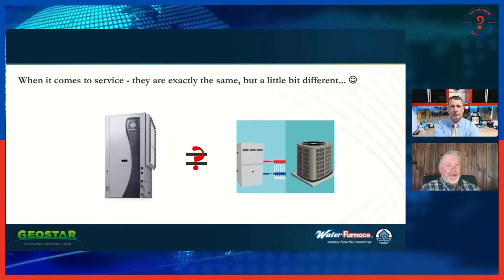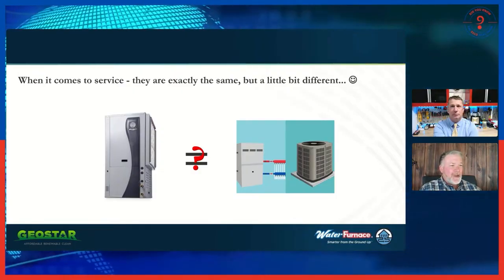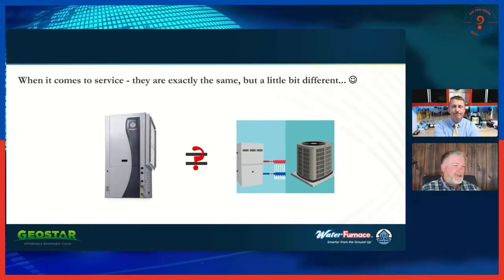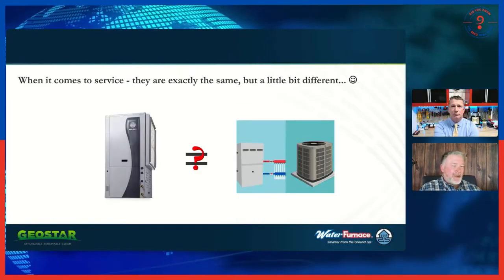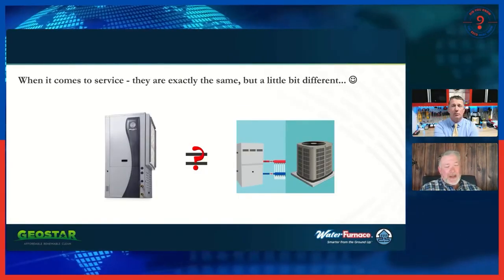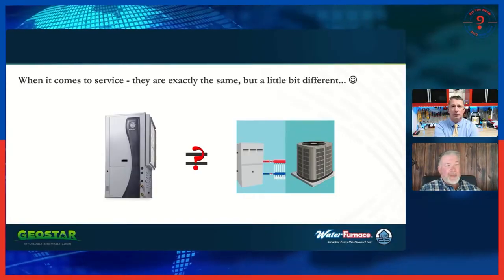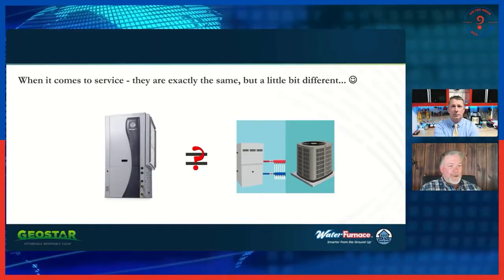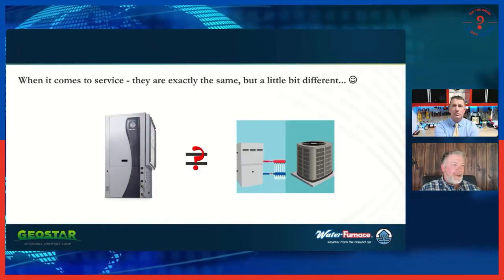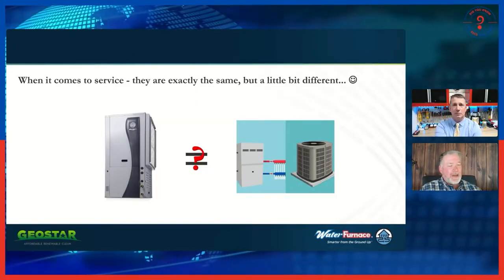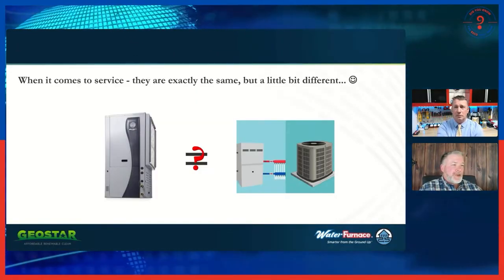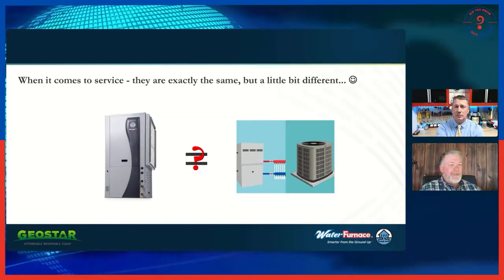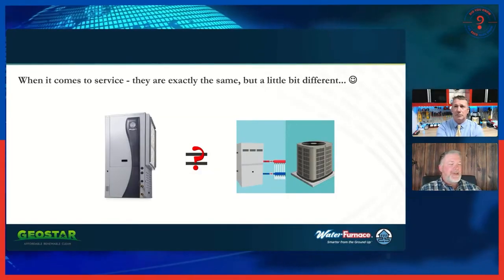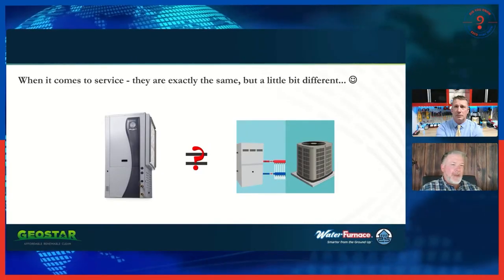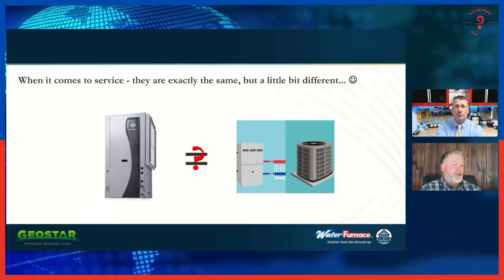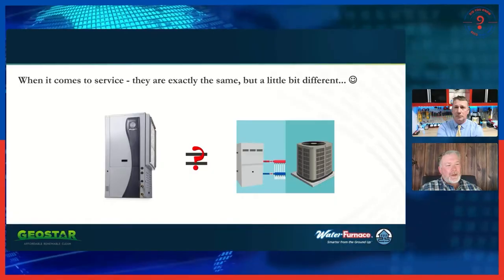Well, they're not exactly the same, but they're extremely similar. Like we mentioned earlier when talking about refrigeration, it all does the same thing - we're moving heat from one place to another. With an air conditioner we're taking heat out of the house and moving it outside; with a heat pump we're taking heat from outside and moving it inside. We do exactly the same thing. The only difference is, instead of having a condenser outside, we've got a loop in the ground. So we're taking heat from the ground through the refrigeration process and putting it into the house, and in summertime we're taking heat out of the house and putting it back in the ground. So really, it functions the same.